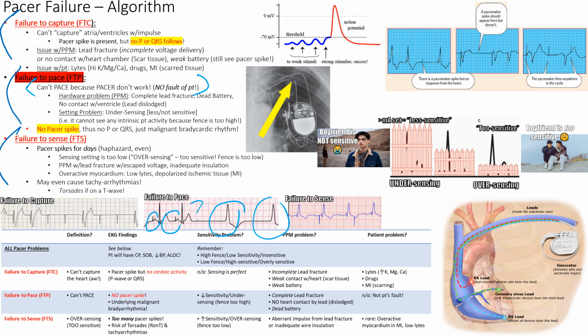And why is it not pacing? It's not the patient's fault, right? It's not like they were the ones that caused this issue. So the pacemaker battery failed. If the battery fails, they're not going to get any pacer spike because there's nothing being generated. There could be a hardware problem where the lead has completely fractured. The signal's being sent, but it stops where the wire broke, and therefore there is no capture. There's no pacing happening. Does that make sense? So either the battery has failed or the wire has completely broken, so there's no contact with the ventricle.